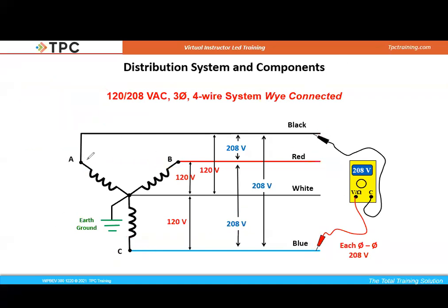So if I went from black to red, I'd get 208. If I went from red to blue, I would get 208. So always on the outside of the system, we get the higher voltage. If we go from the outside to our neutral, we're going to get that lower voltage, which in this case is 120. So usually we have both systems in our facility, right?